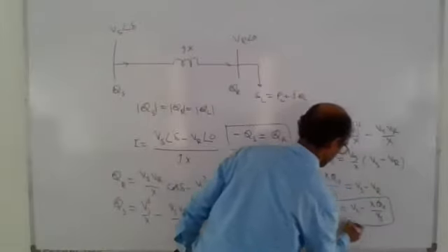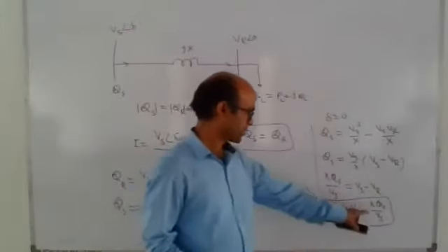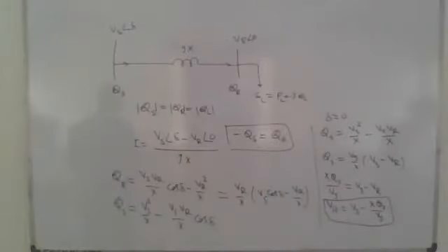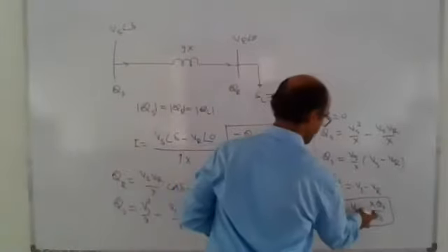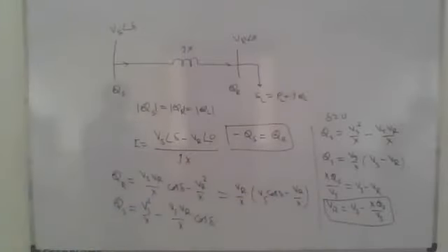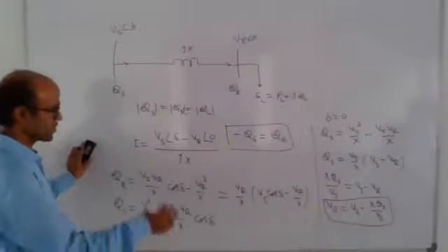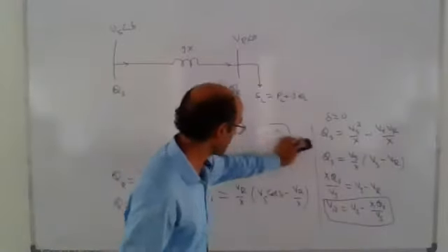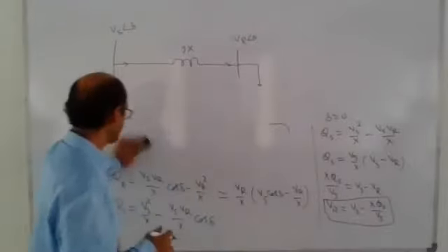So you can see here, if I vary Q, then we can vary the receiving end voltage. So from this it is clear, we can control the receiving end voltage by varying Q, X and VS. VS is the sending end voltage or generator voltage. So there are 3 ways to control this expression, or we can say to control the receiving end voltage in 3 ways.